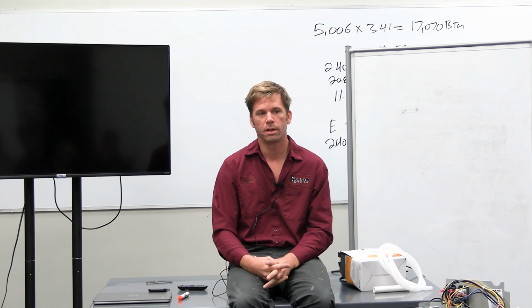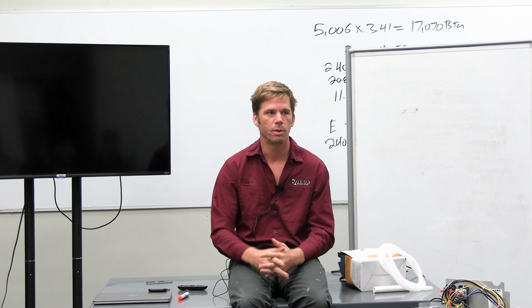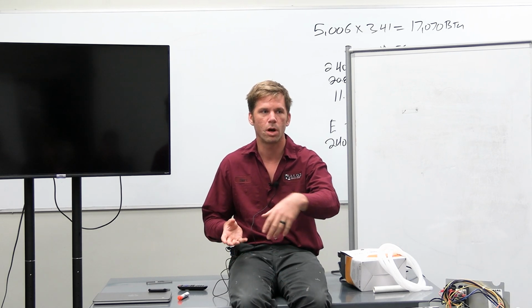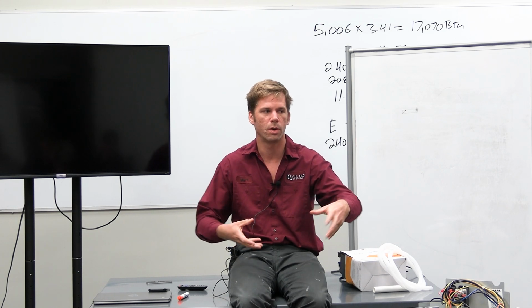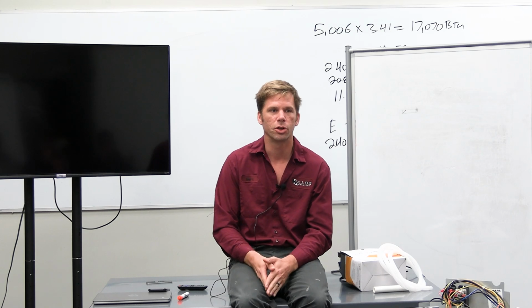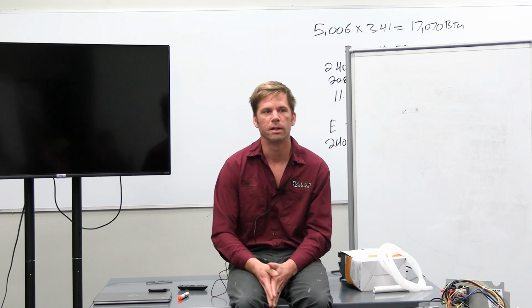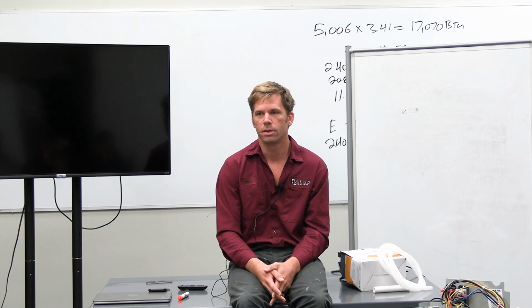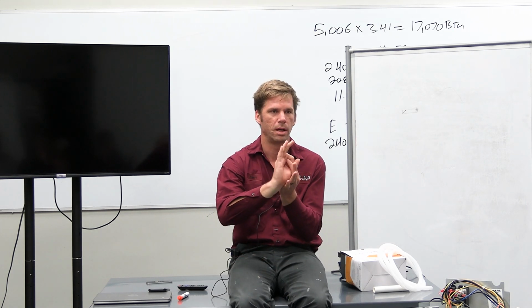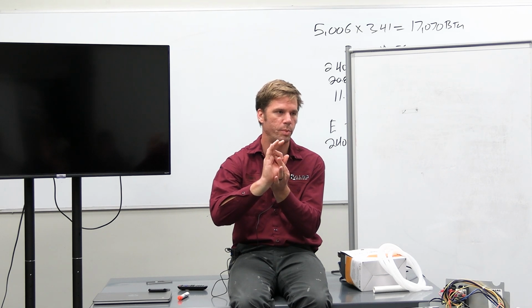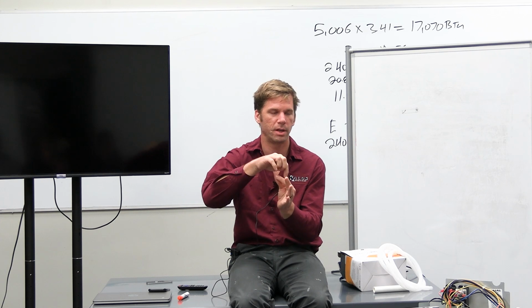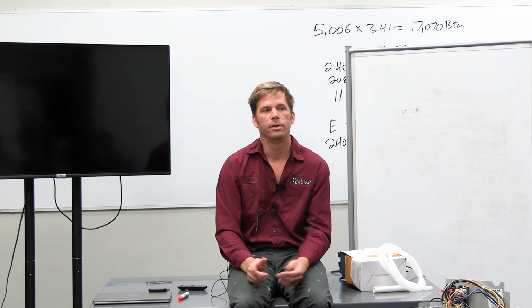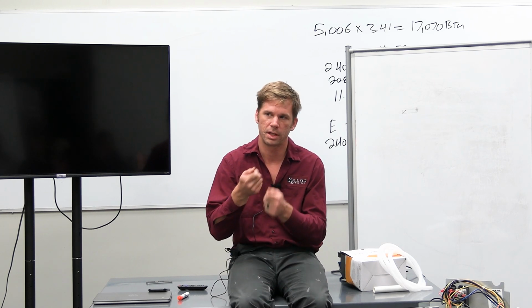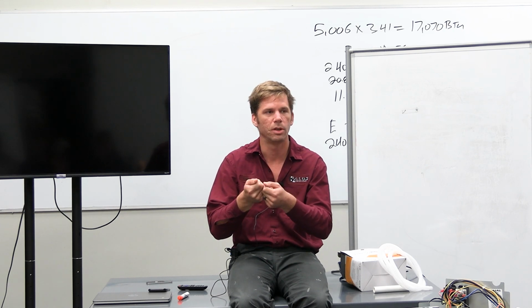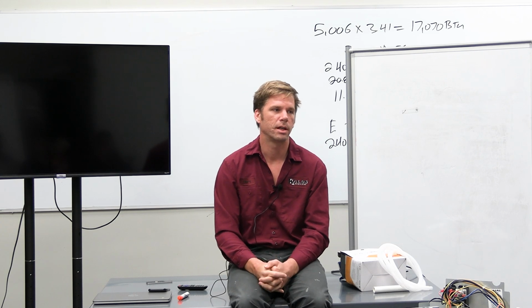And then your other limit safety switches, they're called limit switches. They go in the water on your gas heater, so your water exchanger. Somewhere on there, there are going to be sensors plugged in to make sure that the water coming back to your heater is not hot enough to burn somebody. Those are just little tiny round switches that open when they get too hot. On the side of them, they'll have a temperature rating. You can look at it and see what temperature it's supposed to open at. Those often rust out. The wire connections rust out so badly that you can't read through them, or they crack off. Those are failures that can happen.